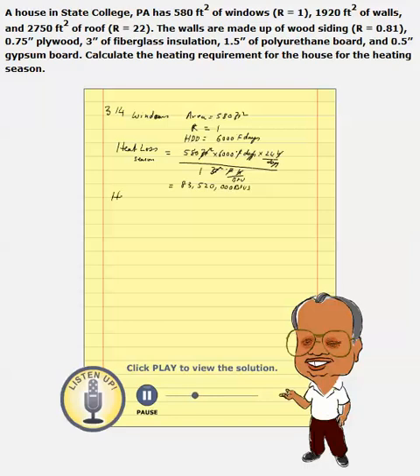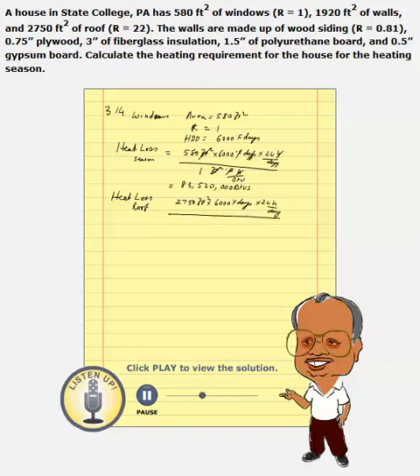Similarly, we can calculate heat loss through the roof. The area of the roof is given as 2,750 square feet, times 6,000 degree Fahrenheit days, times 24 hours per day, divided by an R-value of 22. When you do this calculation, we lose about 18 million BTUs through the roof.